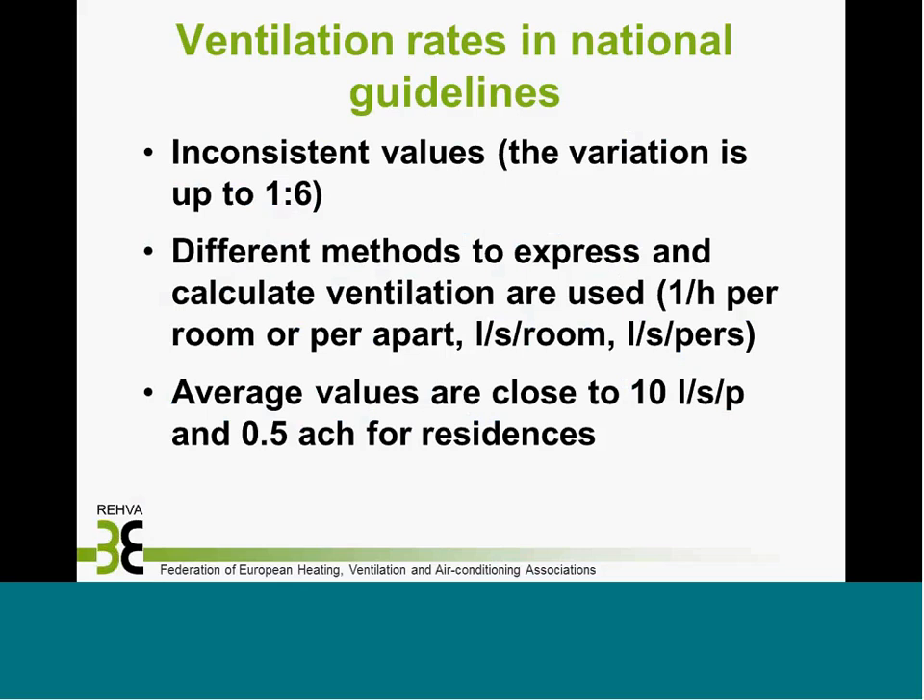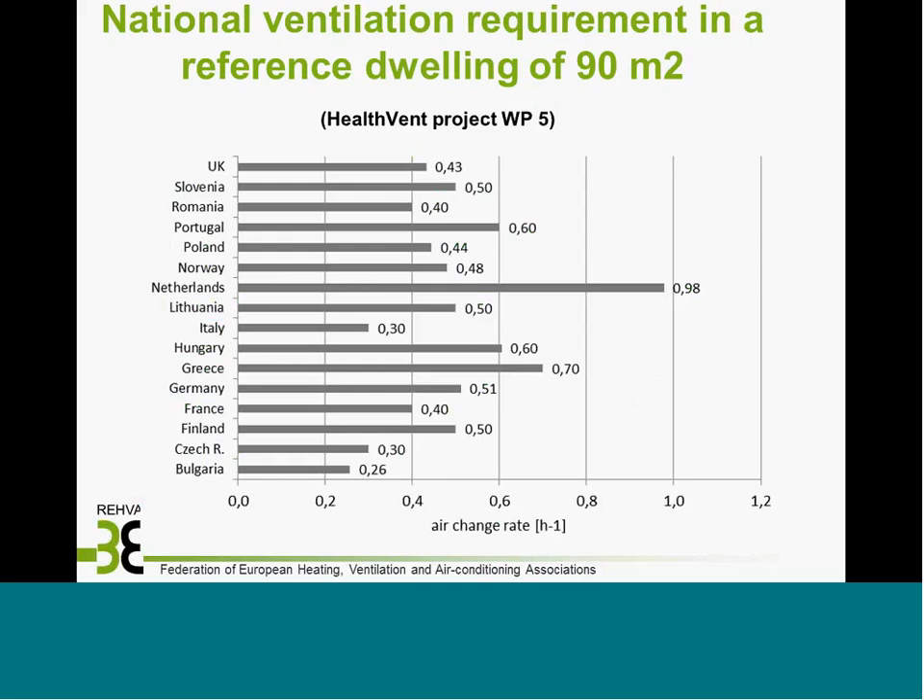The average value seems to be close to 10 liters per second per person in national guidelines and close to 0.4–0.5 air changes per hour for residencies. This slide shows the actual ventilation rates in different countries based on requirements, compared using a reference dwelling — necessary because ventilation rates are defined so differently. There's a huge variation between countries, with the average being around 0.4–0.5 air changes per hour, indicating a clear need to unify and create common guidelines for ventilation rates in Europe.